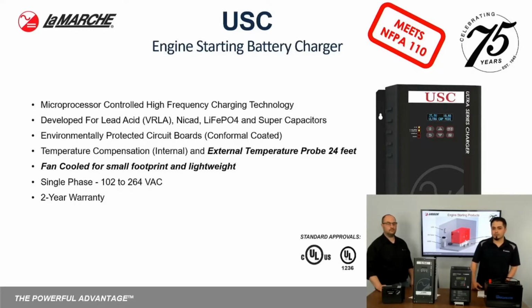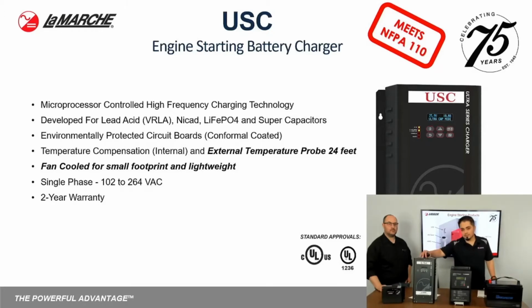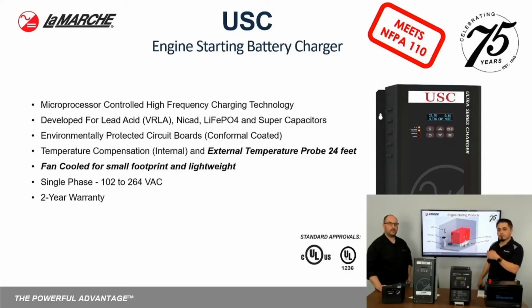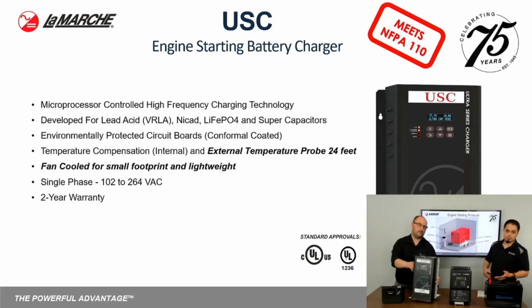We're actually one of the few to have all of the charging technologies able to be charged with one unit itself, without any type of other options. Again, it is conformal coated. There is that protection that is important to us. You do have the temperature compensation internal with your external option. It is fan cooled, so with the fan cooled design, it does allow you to have a much smaller, lightweight package. Very important, especially out in the market where there is competition or other brands have a tighter space or area that this needs to be installed in. And it does give you a wide range of sizes as far as your current ratings as well.